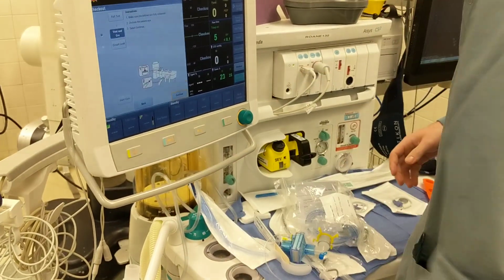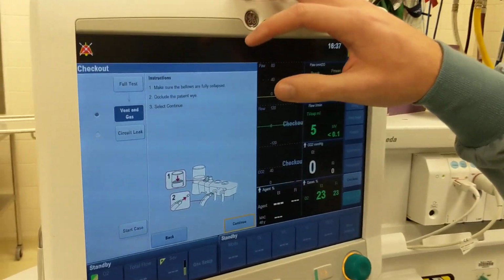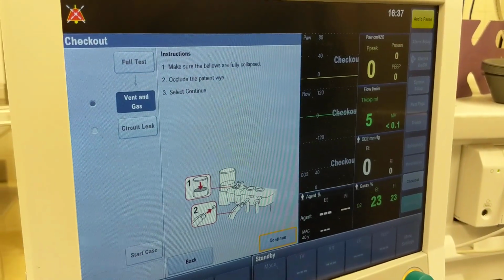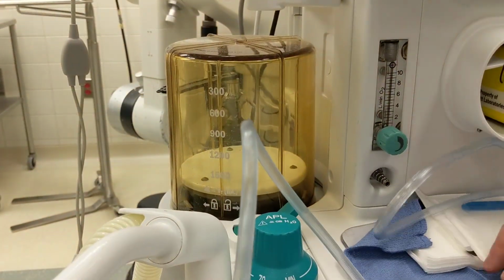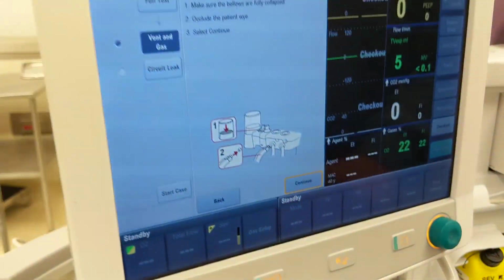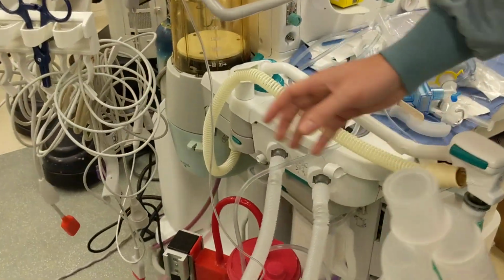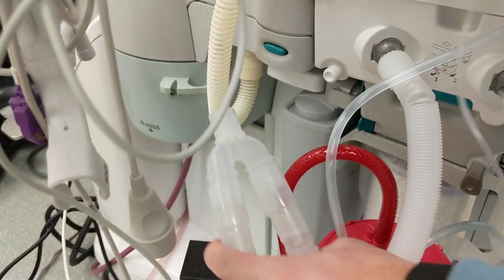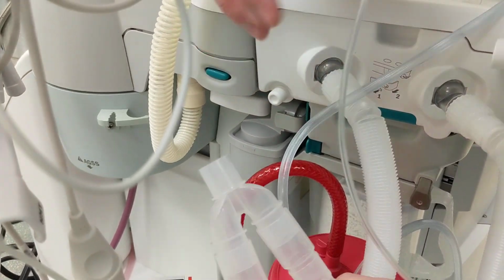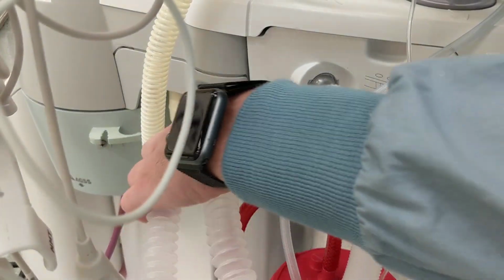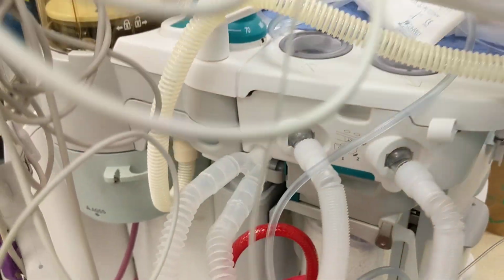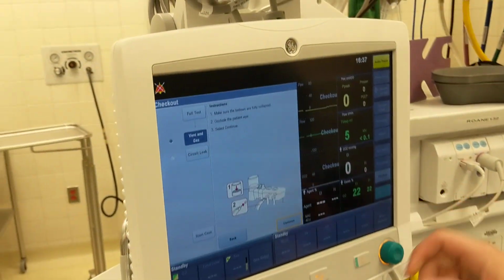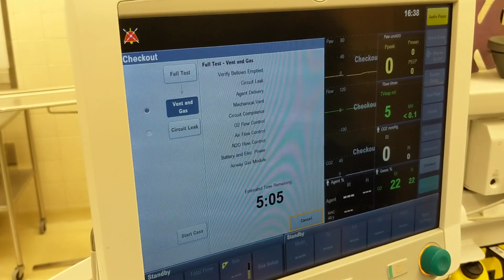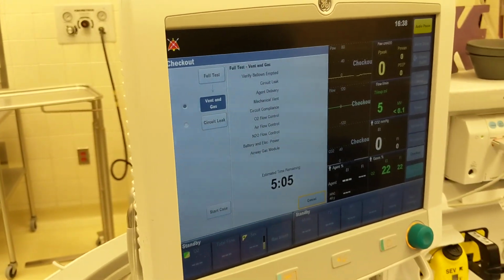In the meantime, the machine is on to the next step. Starting off by making sure the bellows are fully collapsed, and we can see that they are. Occlude the patient Y. We're going to take the patient Y here, and back to where the latch was, right on the side, there's a little knob there to just occlude it, and it fits snugly on there. And you can just hit continue and let the machine run its second step.